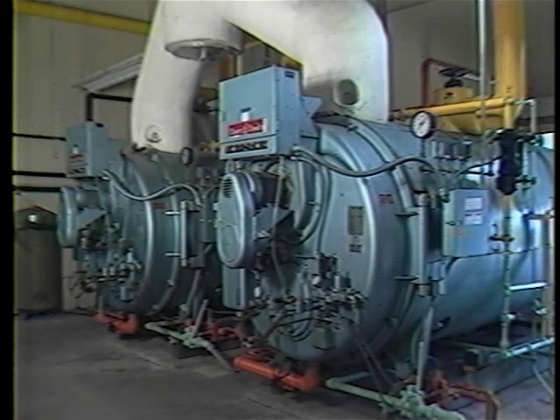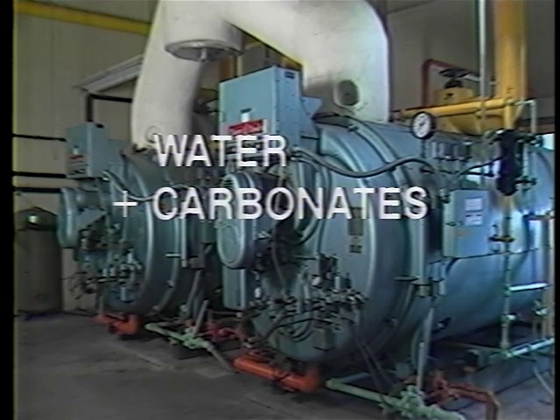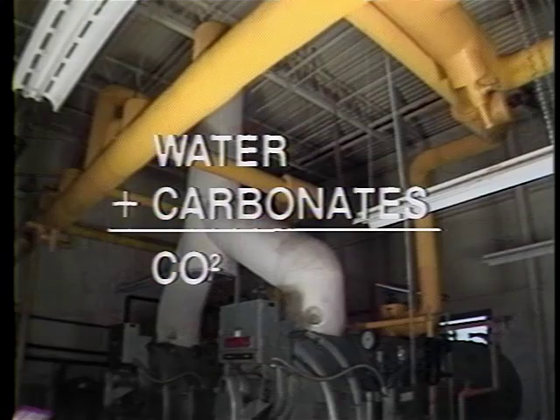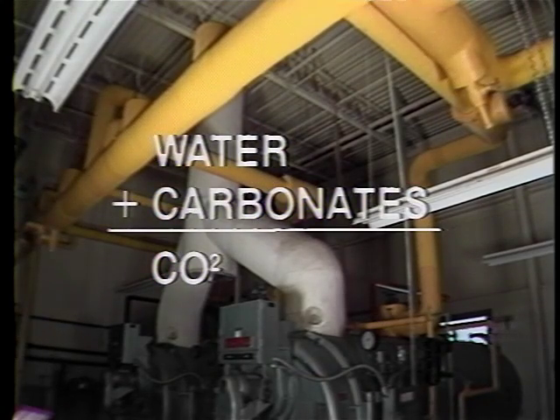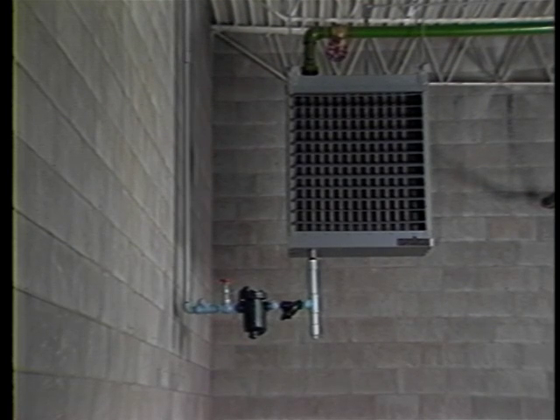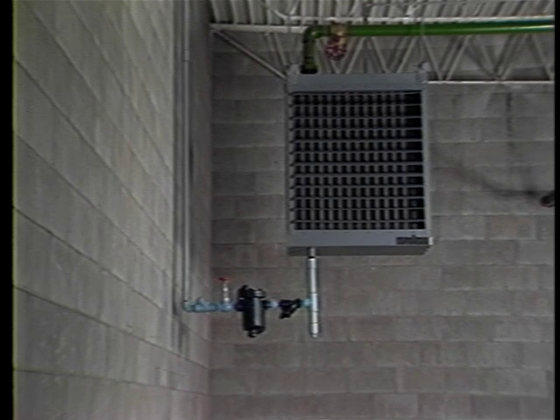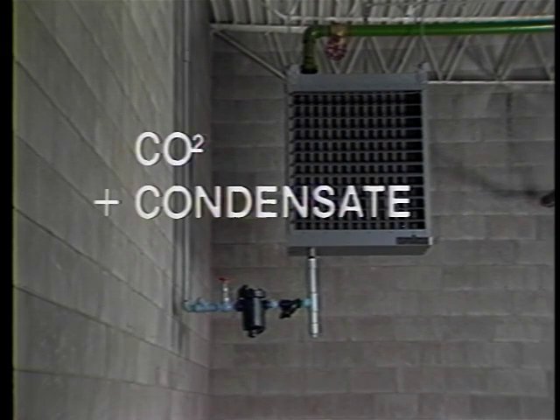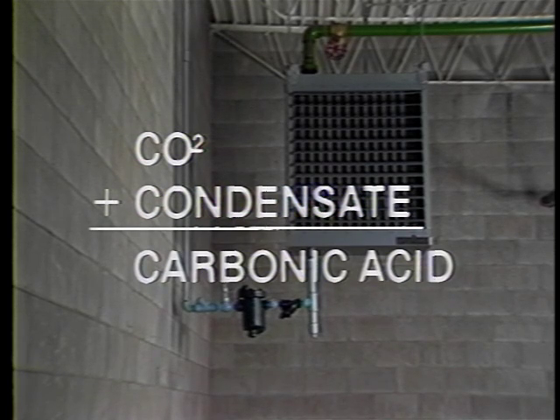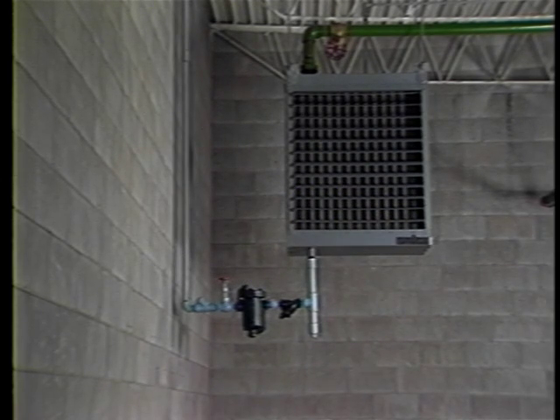Corrosion due to accumulations of condensate starts with the presence of carbonates in the boiler feed water. These carbonates dissolve and release carbon dioxide gas, which then travels with the steam through the distribution piping. If the condensate collects in the heat exchanger and is allowed to cool below the saturation temperature of the steam, these gases will combine with the water, forming carbonic acid. This acid is extremely corrosive and will eventually eat through the tubes in the heater's core, necessitating repair or replacement.